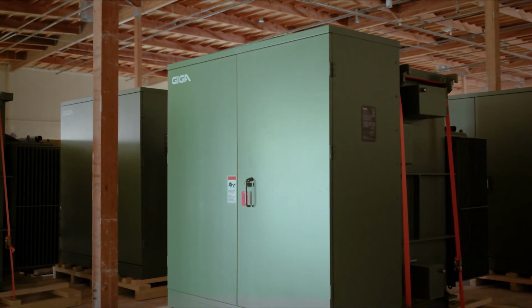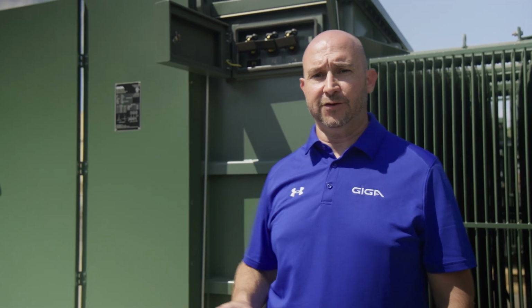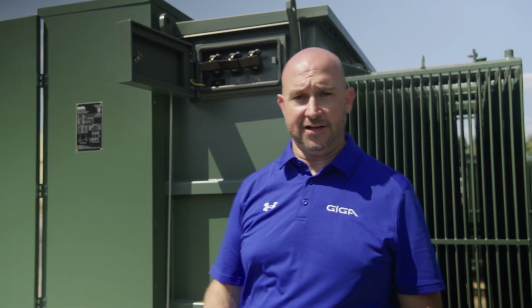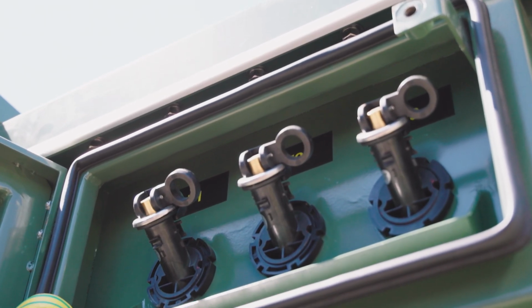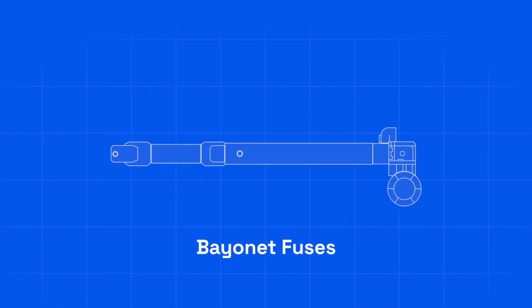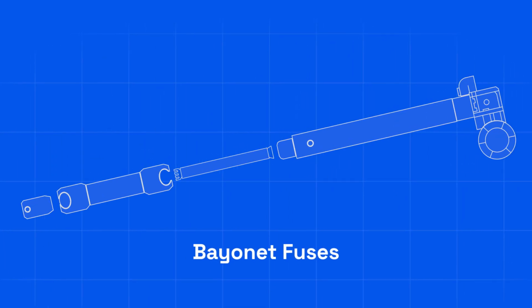A common feature in a Giga transformer is to locate the bayonet fuses here, on the outside of the transformer. Having the bayonet fuses mounted on the outside provides an additional layer of security when de-energizing the transformer by not opening the primary cabinet.